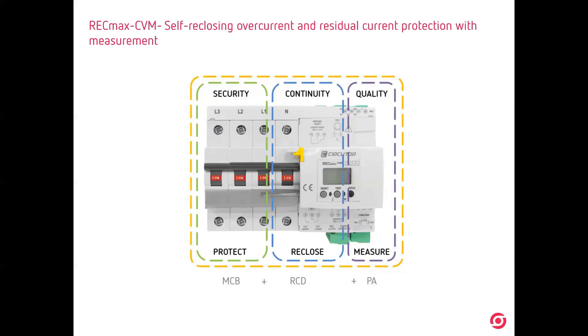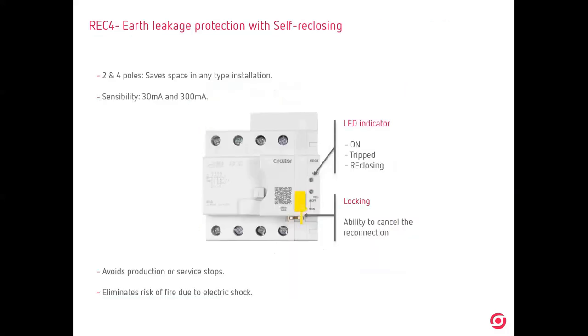And it will reconnect. We have a reconnection system that tries to reconnect with different scales of times, depending on the leakage that we have. And we have a power analyzer. We have the measurement in one device, so MCB, residual current device, and also a power analyzer. More than 250 variables with inputs, outputs, and RS-485 communication to be connected with an EMS software. But this is direct, up to 63 A, with self-reclosing systems.